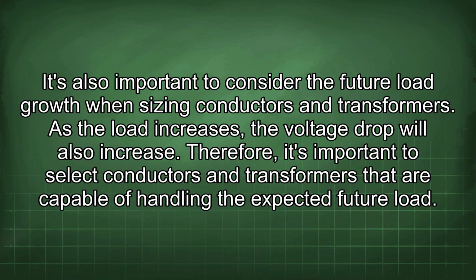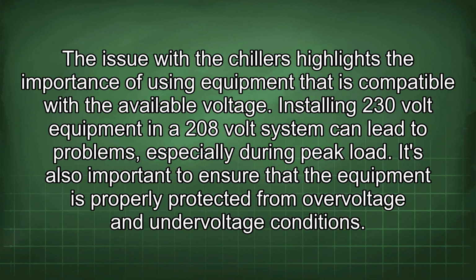It's also important to consider future load growth when sizing conductors and transformers. As the load increases, the voltage drop will also increase. Therefore, it's important to select conductors and transformers that are capable of handling the expected future load. The issue with the chillers highlights the importance of using equipment that is compatible with the available voltage. Installing 230 volt equipment in a 208 volt system can lead to problems, especially during peak load.